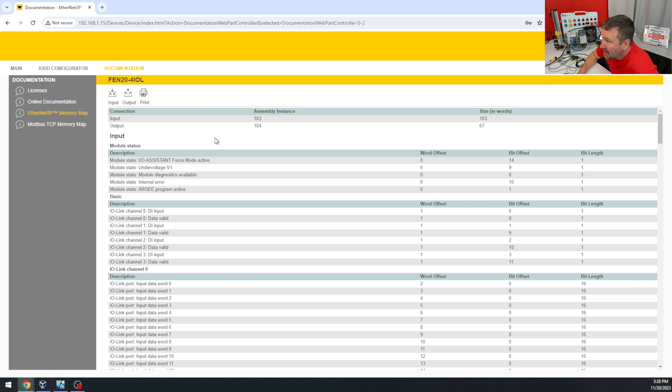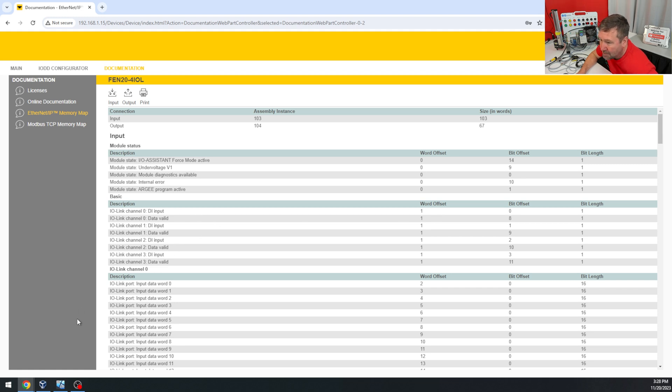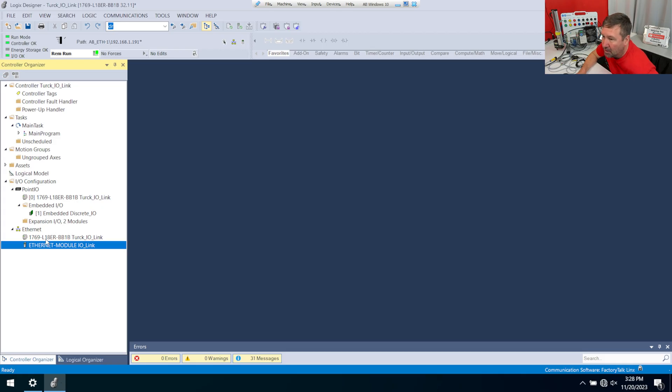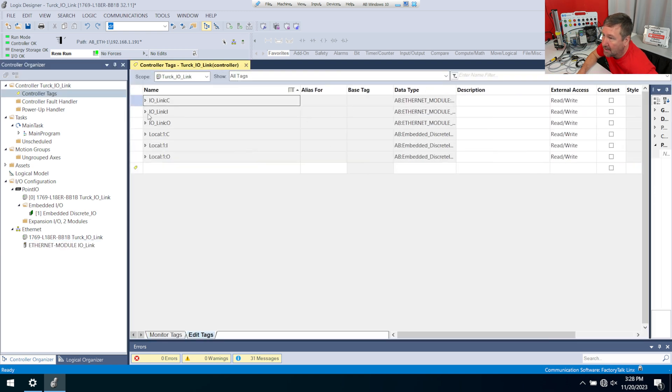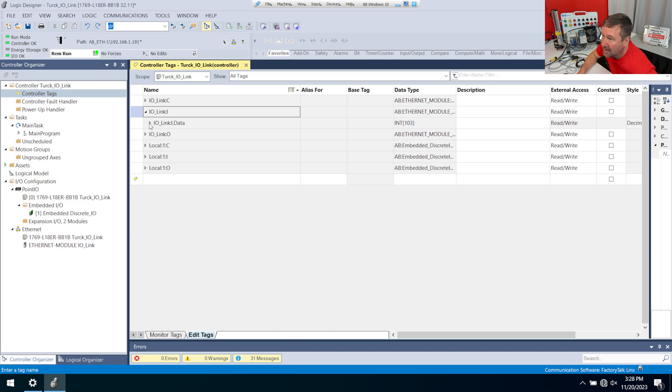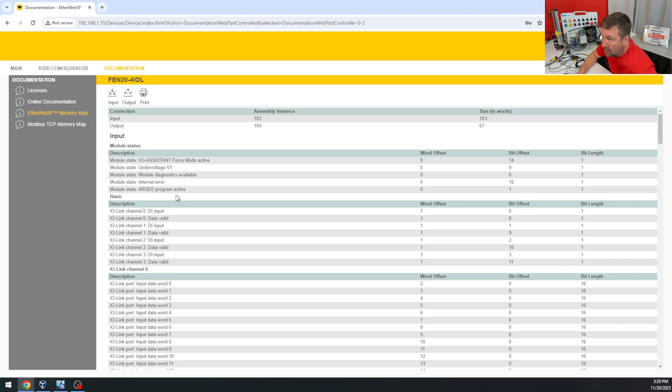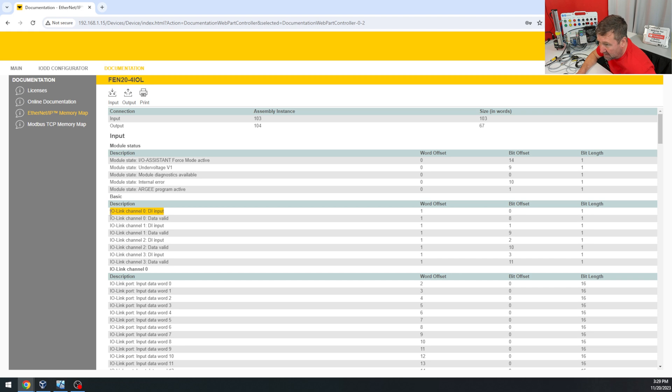So if we look here, we have some diagnostic data in word offset zero, but then one looks like our actual data. So if we go over here and we got our controller tags, we have IOLink:I.Data in word offset one, we should be able to see the basic inputs of our IO-Link. So IO-Link channel zero is going to be bit offset zero.